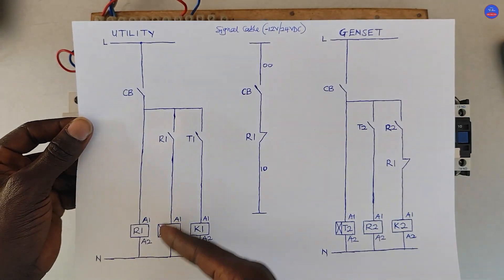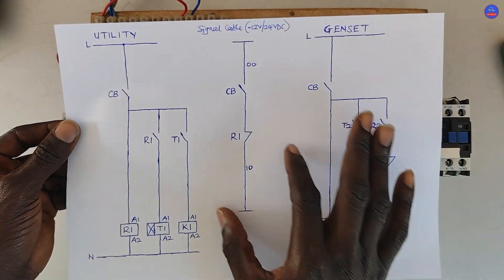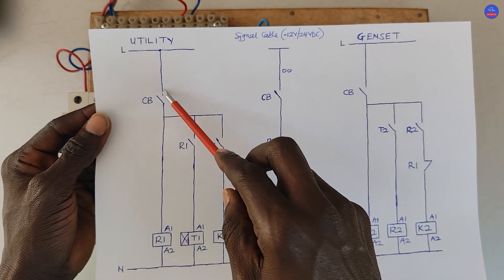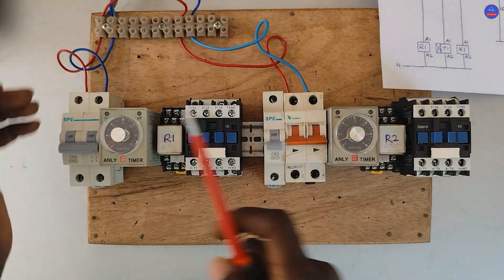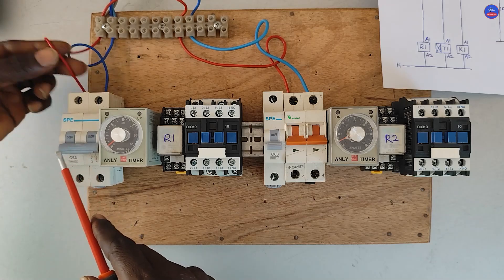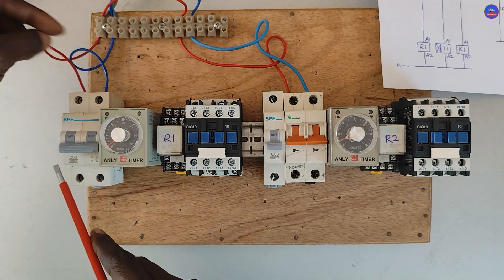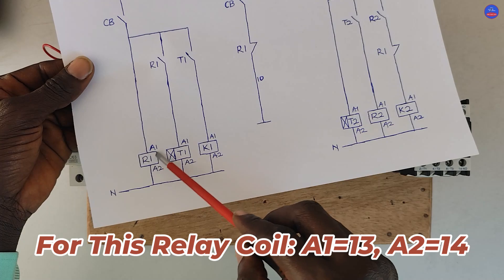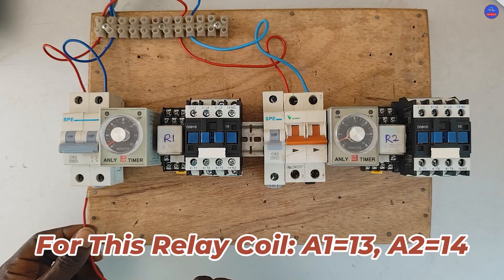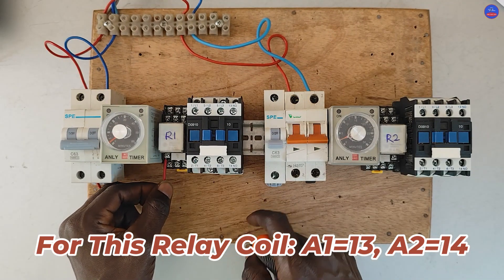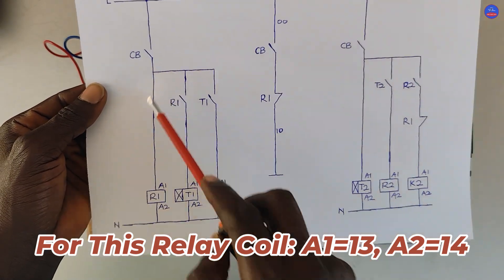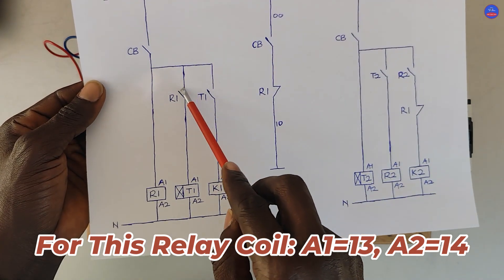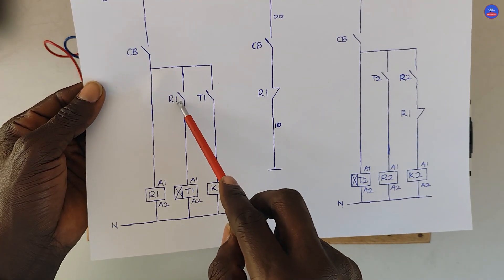This is the utility line and then this is the genset line. We tap from the live line to one side of the breaker. This is the breaker — this is the live, this is neutral. From the output of the breaker, it goes to A1 on the relay. We can tap from the output of the breaker or from A1 on the relay to one side of the open contact on the relay.